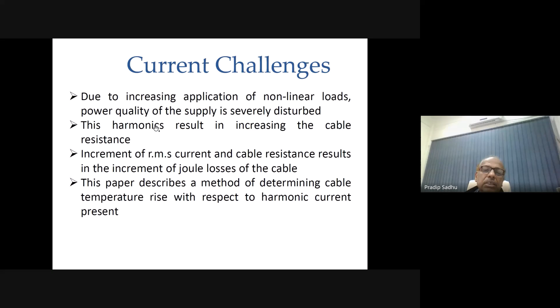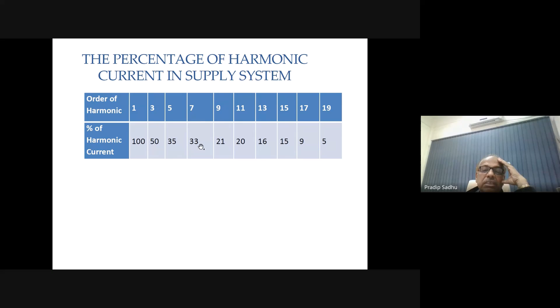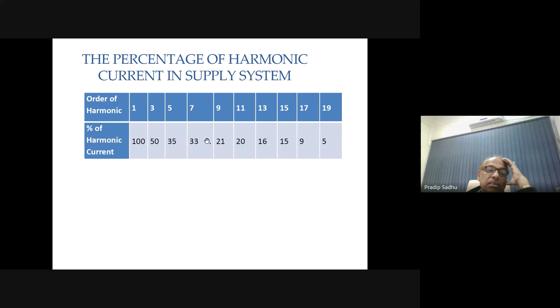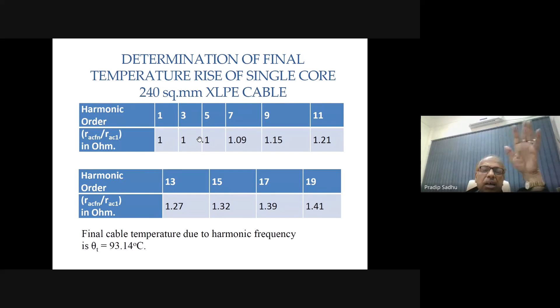So you will see that due to this cable power transmission, 100% is the fundamental, the third order is 50%, 35%. These higher order harmonics will create heat over the cable, and that will shorten the life of the cable. So if you have interest, you will get this. We will conclude this experimental procedure. That means condition monitoring is required.